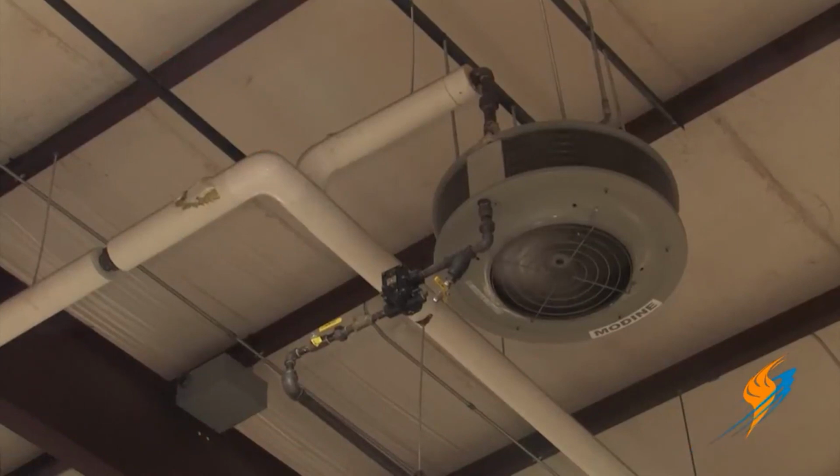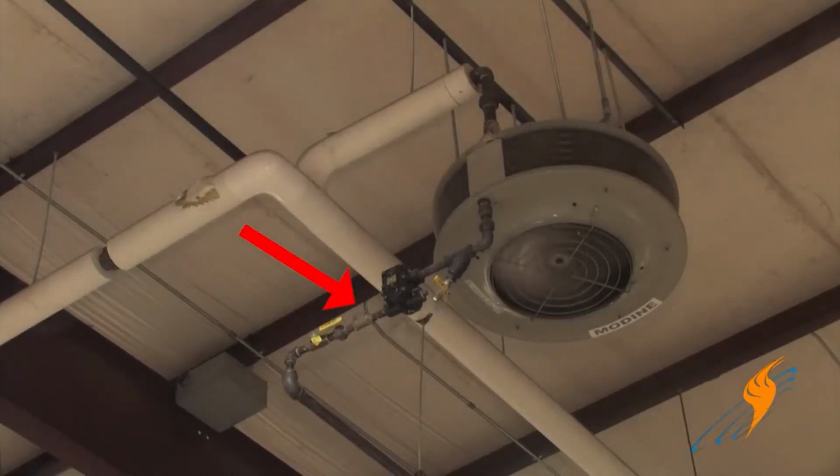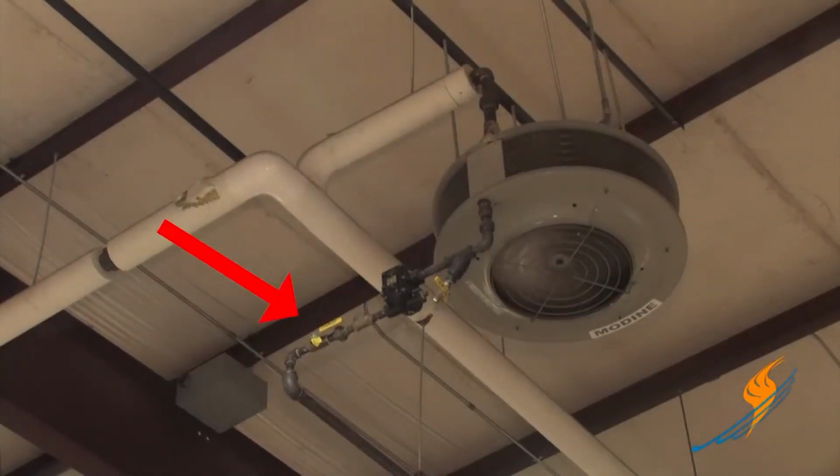Coming out of the unit heater, we've got a strainer with a blowdown valve. We've got a float and thermostatic trap, which should be able to handle large amounts of condensate we may have from a unit heater. And then we have a check valve so that we don't back condensate up into the unit heater if the steam system's shut down. Finally, we've got one last valve so that we can isolate the unit completely if we need to for service.